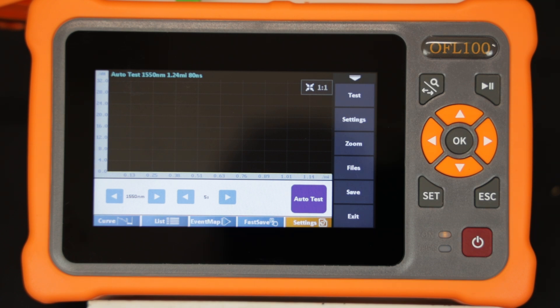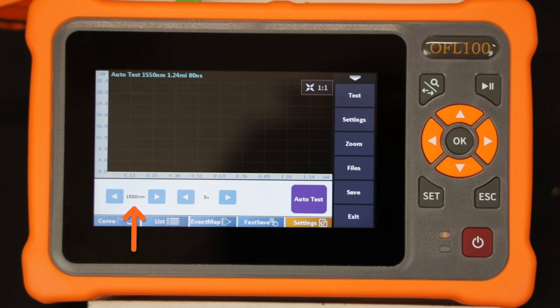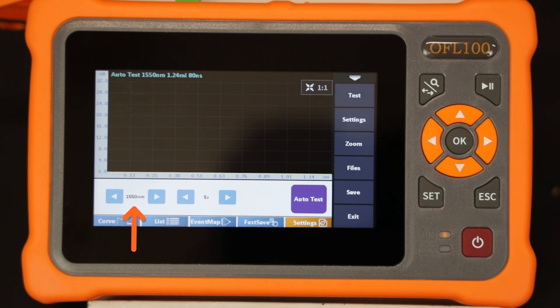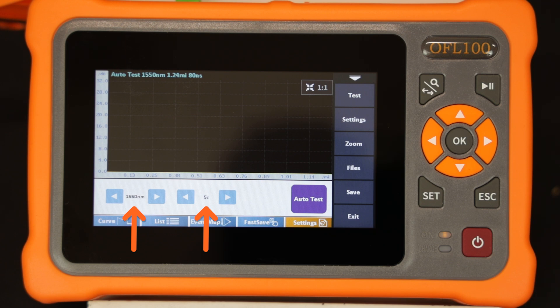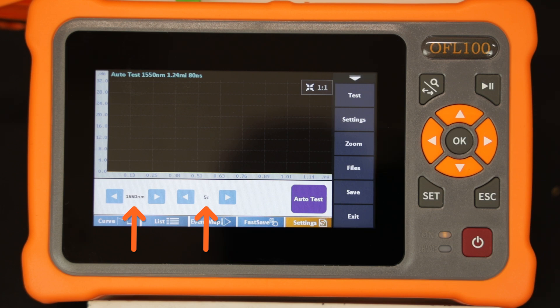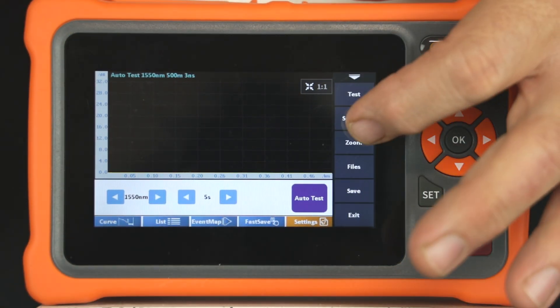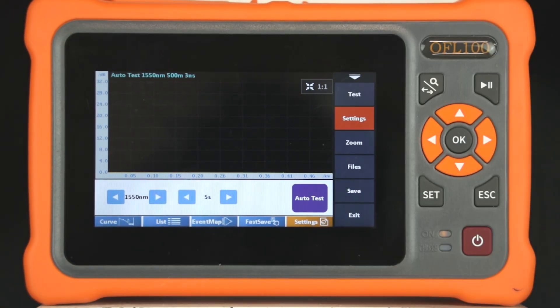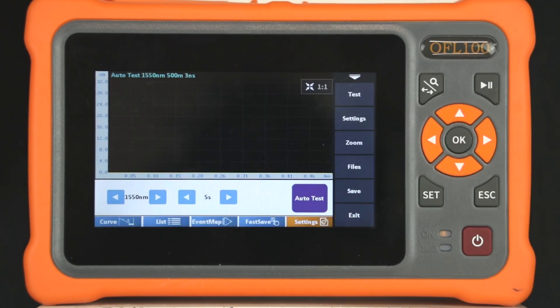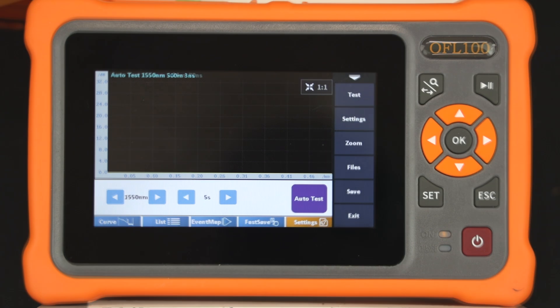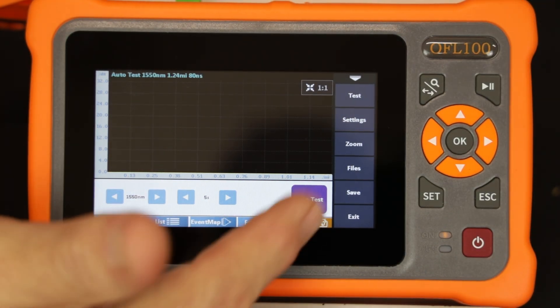The optimum range and pulse width are automatically determined by the OFL100. The technician does have the option to toggle between 1310 nanometers and 1550 nanometers and to adjust the length of the averaging time. The technician can also access these settings using the vertical row of soft keys on the right hand side of the screen. Push the settings key. The refractive index can also be set at this time as required. Pushing the auto test button will start a measurement.